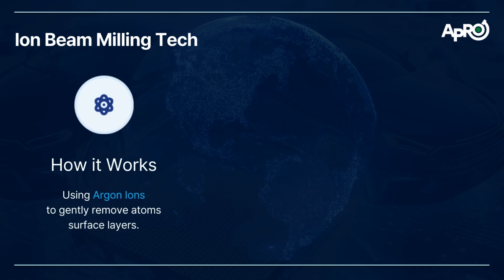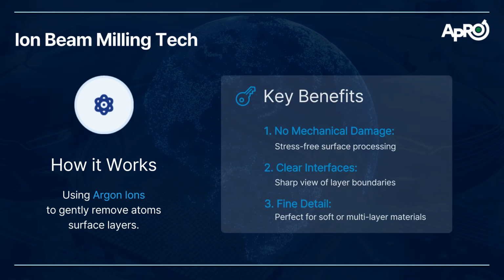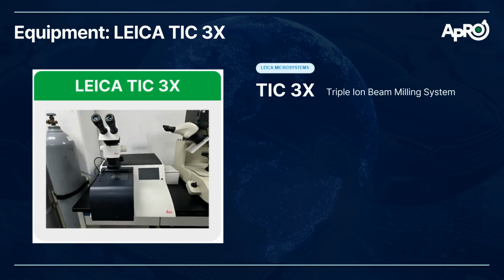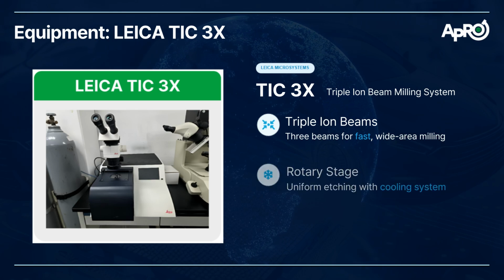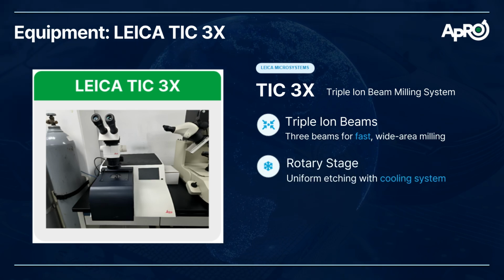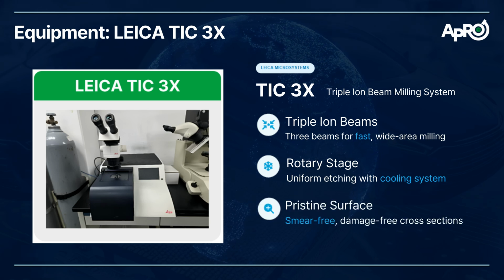Ion beam milling uses argon ions to remove surface layers. It provides clear interfaces without mechanical damage and reveals fine microstructural details. We use the Leica TIC 3X triple ion beam system. It enables fast milling, uniform etching with a cooling system, and produces pristine surfaces without smearing.